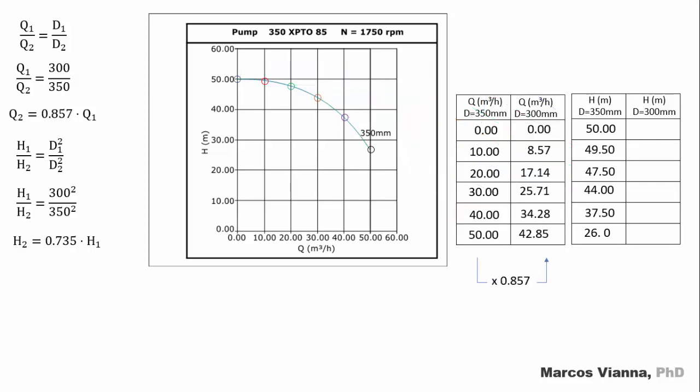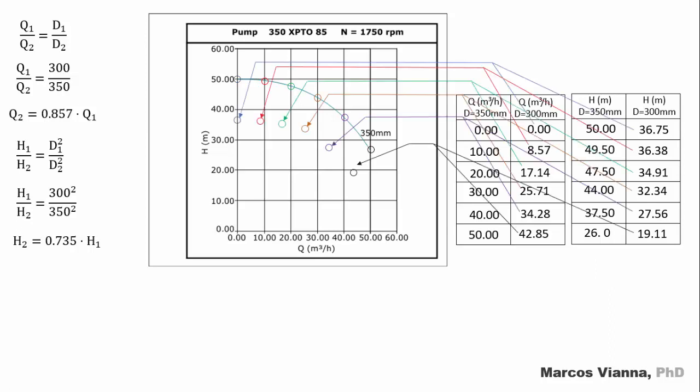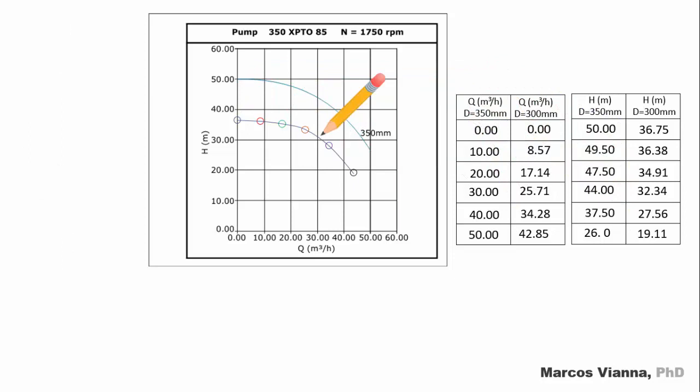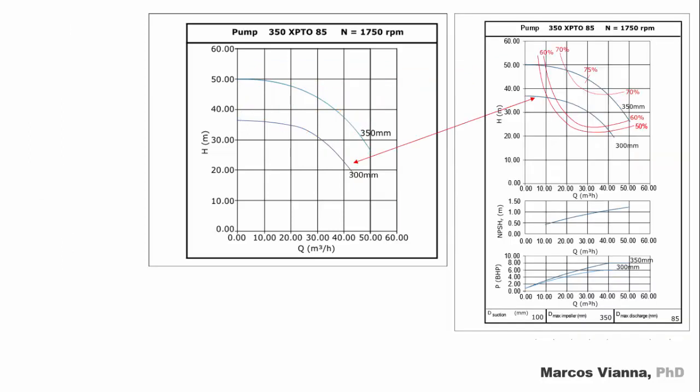Now we fill the right column of the left table, multiplying each flow by 0.857, and the right column of the right table, multiplying each head by 0.735. The new pairs of values head versus flow are now transported to the graphics. The dots are united with the pencil. And there is the curve that we were looking for.